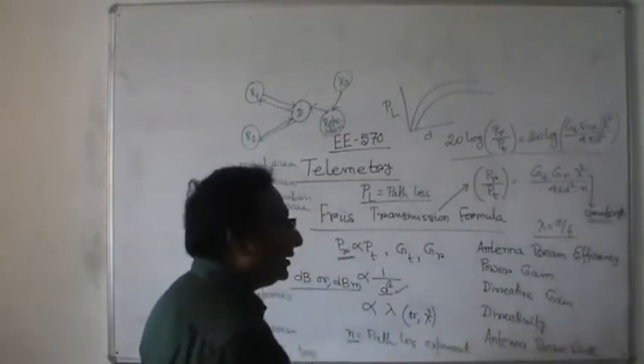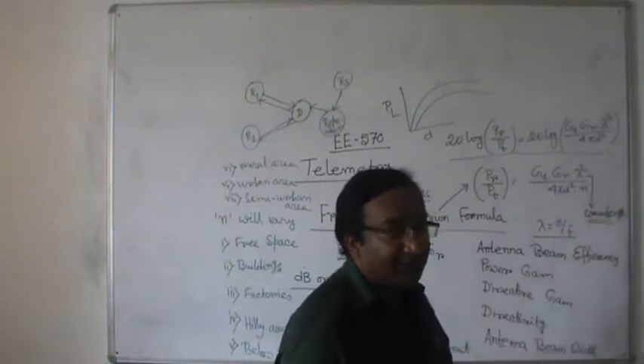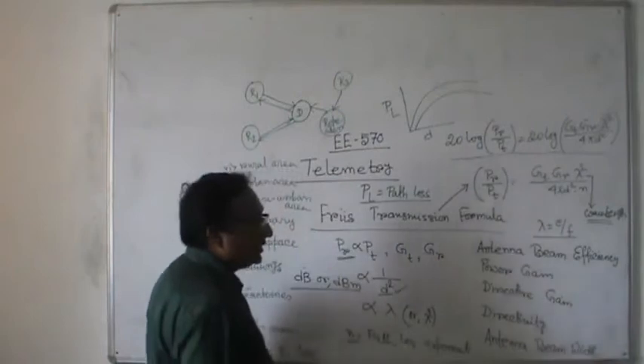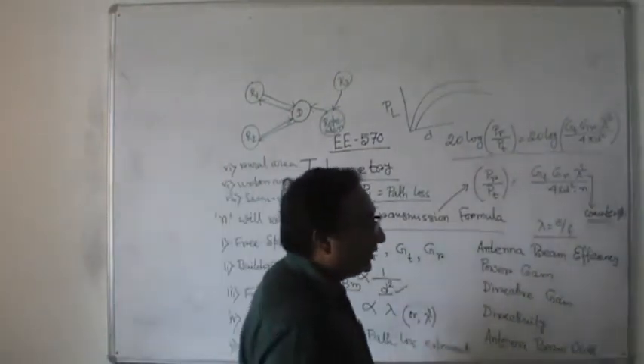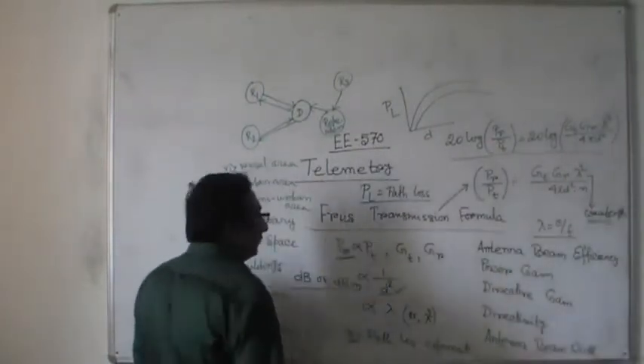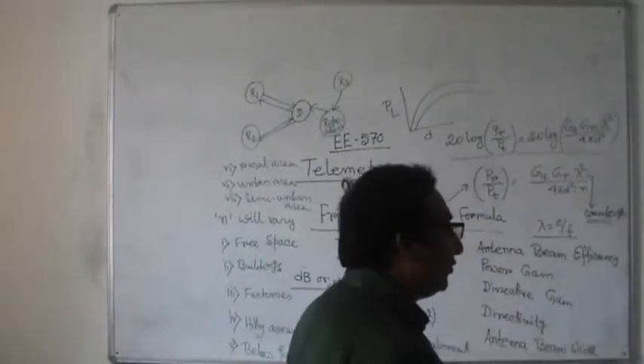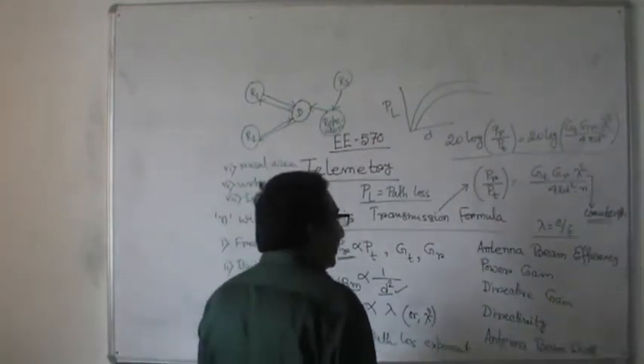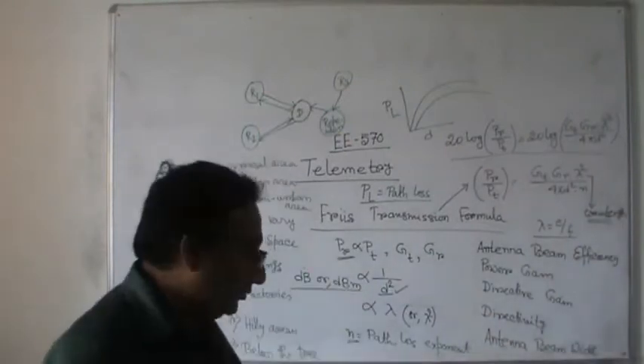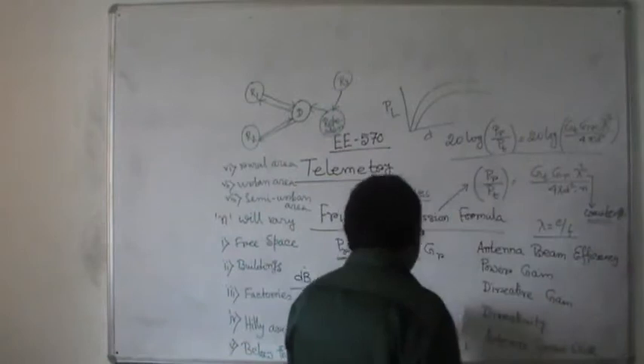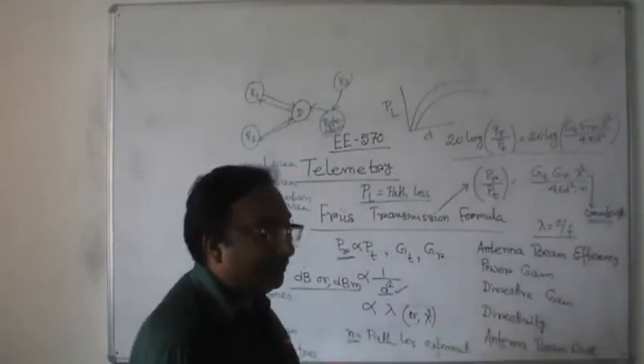Now, what are the types of wireless telecommunication in terms of telemetry? As I told before, there will be VHF at 150 to 174 MHz, then UHF at 420 to 470 MHz, and there is also a 900 MHz band going up to 960 MHz. There will be cellular telephony, spread spectrum telemetry, and satellite telemetry. Satellite telemetry is used for remote monitoring sites where there is no cellular coverage.